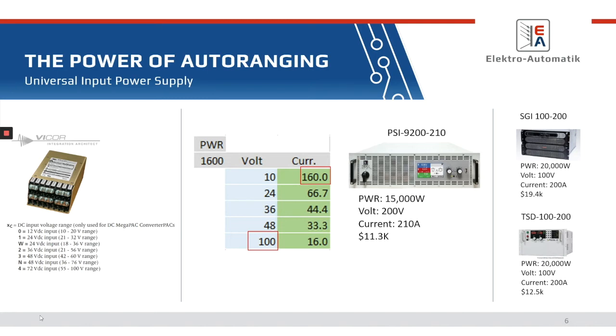And so what you'll see here is that you need to achieve both the 100 volts, but you'll also need to achieve the 1600 watts. 10 volts equals 160 amps. So the customer, to test this 1600 watt power supply, is basically going to have to get a 100 volt, 160 amp power supply to be able to drive this. What you'll see on the right is the various solutions. The first one you'll see is an auto-ranging power supply, right? It's 15 kilowatts, obviously plenty of power, 200 volts. So it's twice the voltage that's needed. And the current is slightly higher, at 210 amps.